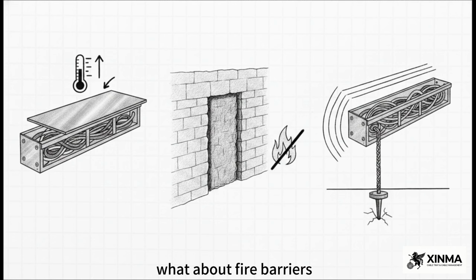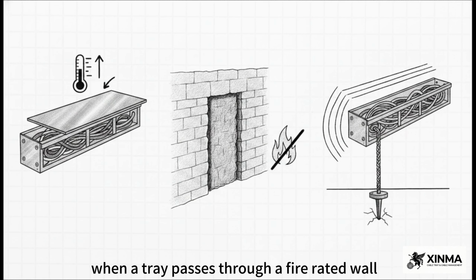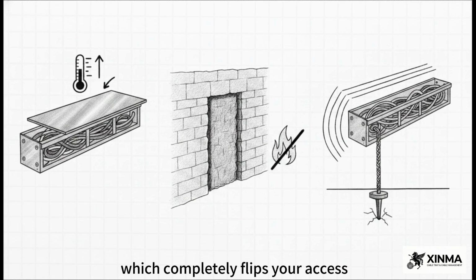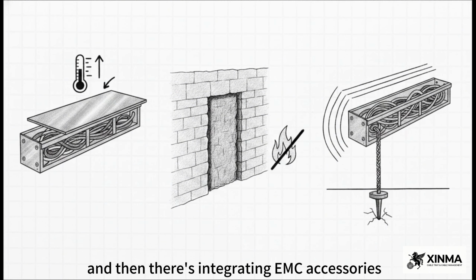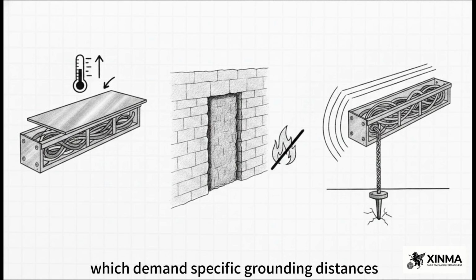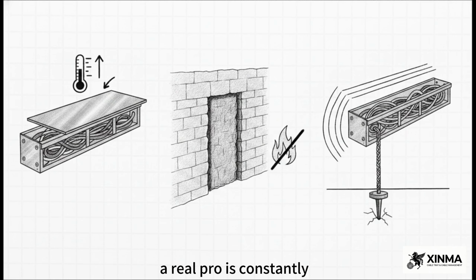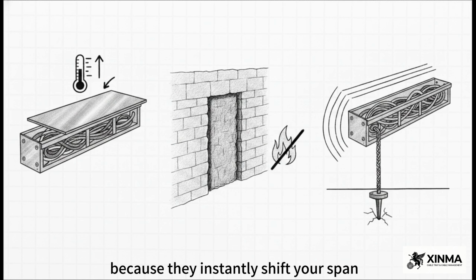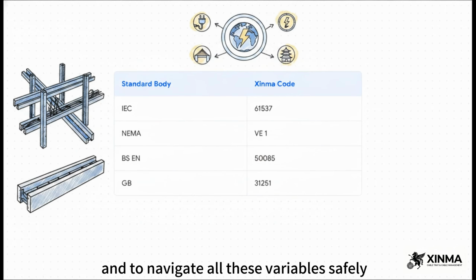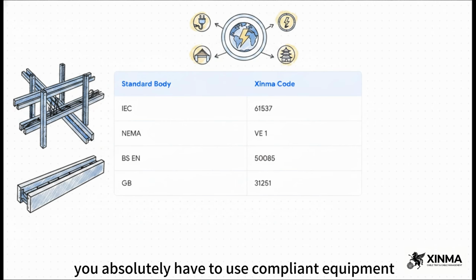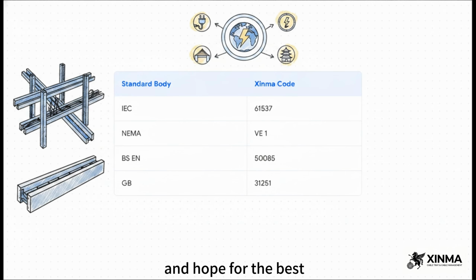What about fire barriers? When a tray passes through a fire-rated wall, it gets packed with intumescent material, which completely flips your access and routing dynamics. And then there's integrating EMC accessories, which demand specific grounding distances to prevent data corruption. A real pro is constantly dynamically managing these variables because they instantly shift your span and fill decisions. And to navigate all these variables safely, you absolutely have to use compliant equipment. You can't just bend some sheet metal and hope for the best.